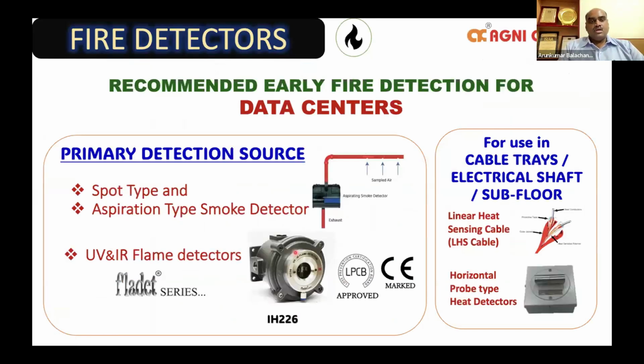So as a primary detection source, it is always recommended to go for a spot type smoke detector and an aspiration type smoke detector, depending on the size of the data center, along with the secondary detection of flame detectors using IH226, the UVIR flame detector. Sometimes many people try to use only a UV flame detection, and we as a manufacturer do not recommend it because the data center is a very high and critical risk area. Using only one parameter, that is the ultraviolet, is very highly prone to give false alarm. That is the reason, as a manufacturer, we recommend a UV and IR combined flame detector, which is false alarm immune detection, and also a very quick detection source.